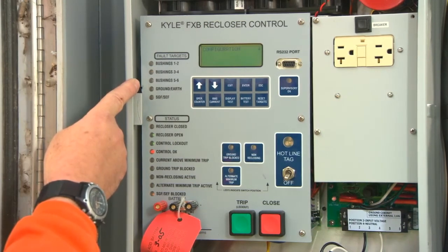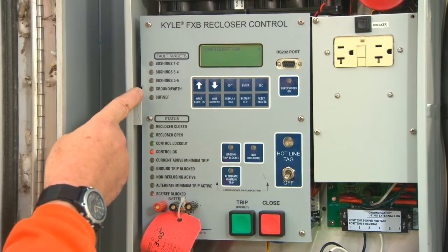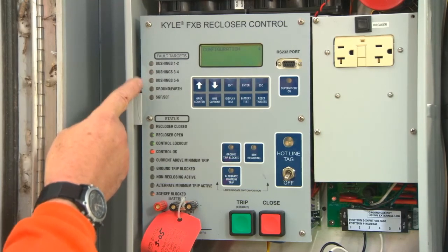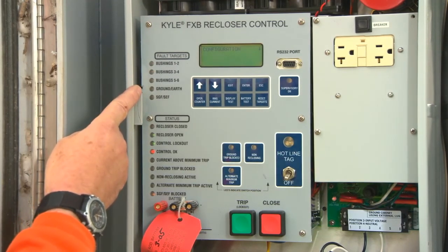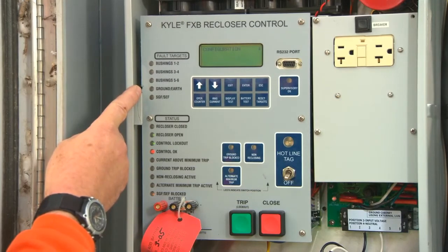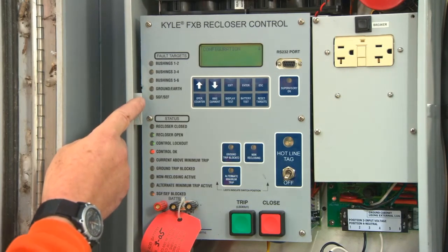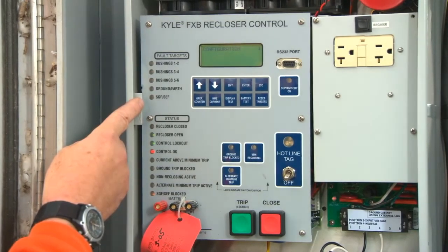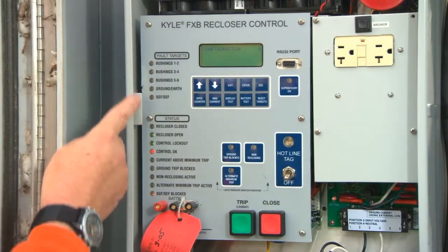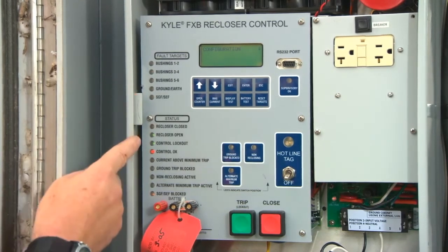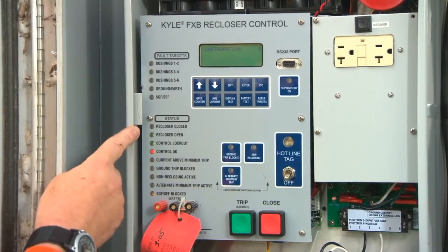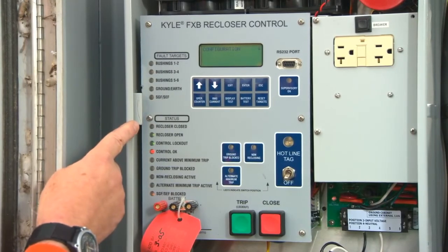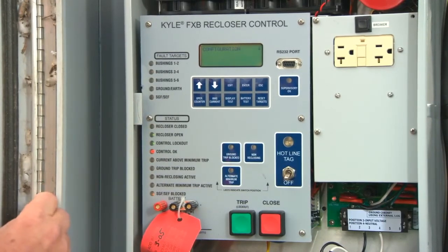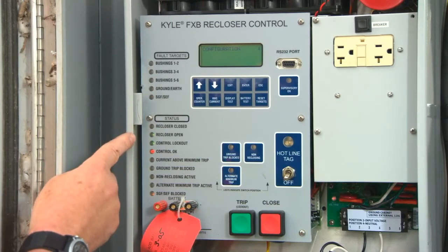The ground LED indicator will tell you if you've had a ground fault. All of these bushings will activate under phase fault conditions, identifying which phase has faulted. The sensitive earth SGF-SEF function is not active in this control, therefore the indicator will stay off. When active, this indicator will become red. Moving down to the next group, we have the status indicators. The first is recloser closed, followed by recloser open. As you can see now, the recloser is open, as indicated by a green LED.